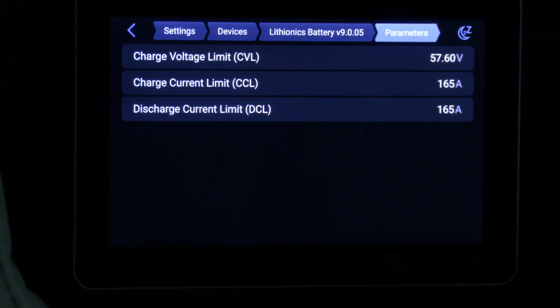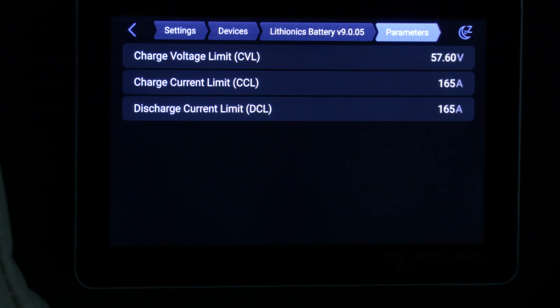By the way, the charge current limit and charge voltage limit are actually coming from the battery management system. So the Lithionics battery says, hey, right now I want to charge at 57.6 volts, and you can give me up to 165 amps. That goes out on the bus and tells the alternator, or the inverter charger, to charge at that limit.